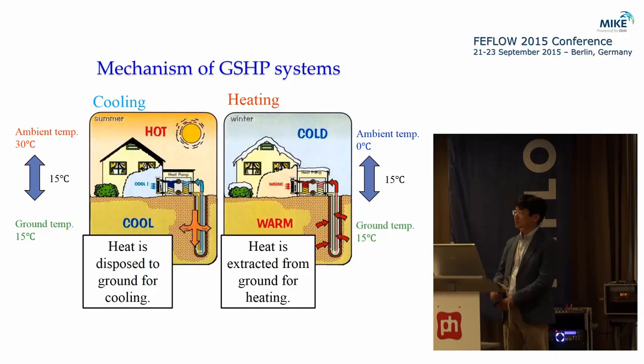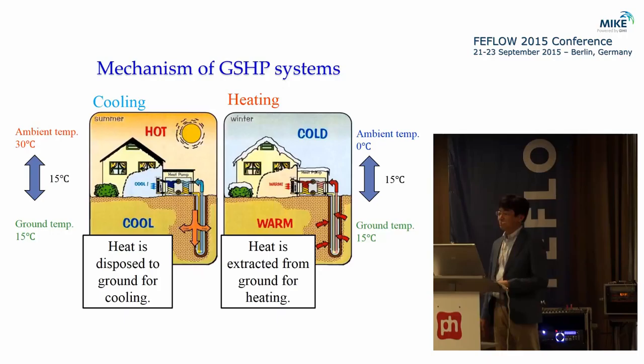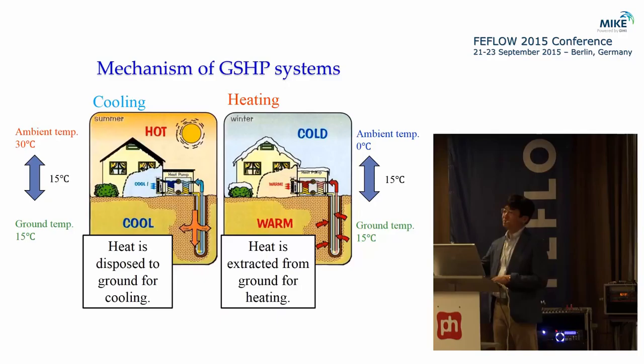This schematic shows the mechanism of ground source heat pumps. We drill a heat exchange well, which is usually 50 to 200 meters deep, near a building or house where we carry out air conditioning. The shallow ground temperature is almost constant below minus five meters or so. In our hometown Akita, the temperature is 15 degrees C.